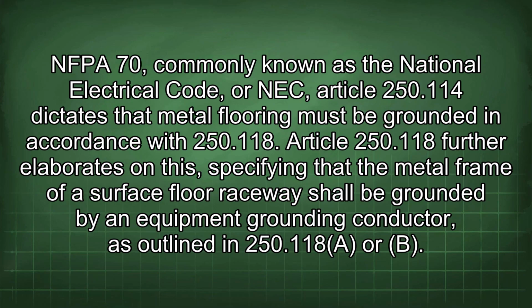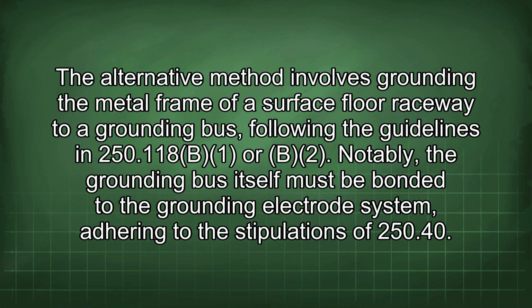NFPA 70, commonly known as the National Electrical Code, or NEC, Article 250.114 dictates that metal flooring must be grounded in accordance with 250.118. Article 250.118 further elaborates on this, specifying that the metal frame of a surface floor raceway shall be grounded by an equipment grounding conductor, as outlined in 250.118 A or B. The alternative method involves grounding the metal frame of a surface floor raceway to a grounding bus, following the guidelines in 250.118 B1 or B2. Notably, the grounding bus itself must be bonded to the grounding electrode system, adhering to the stipulations of 250.40.